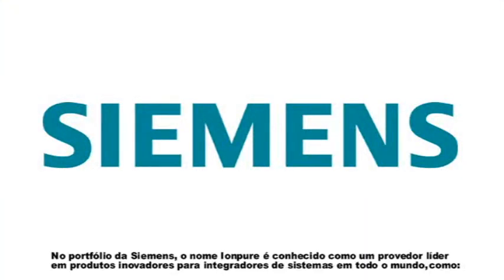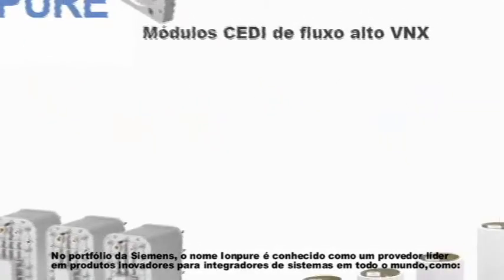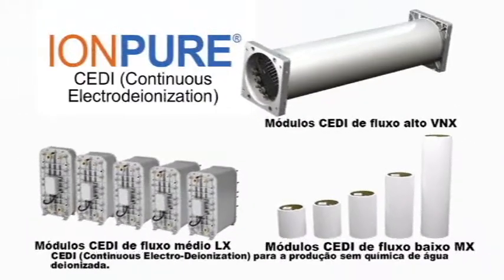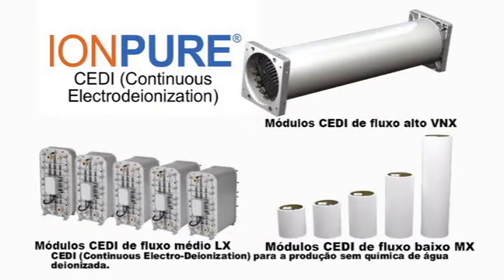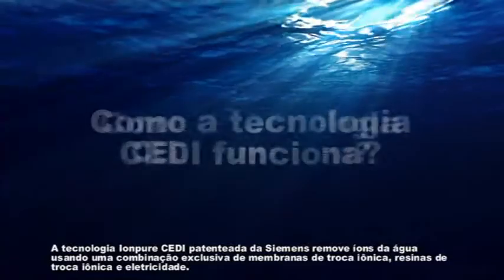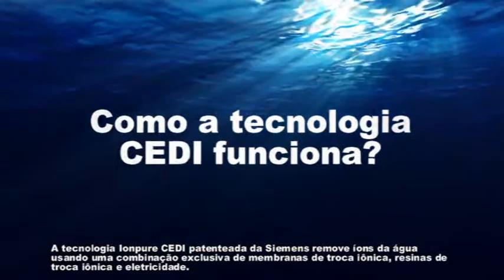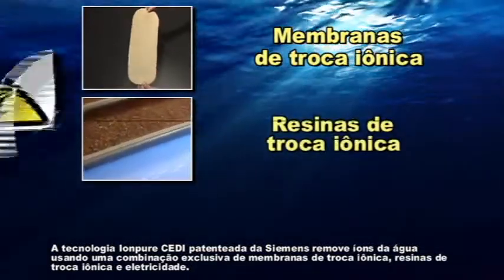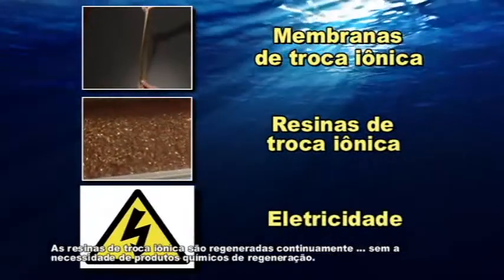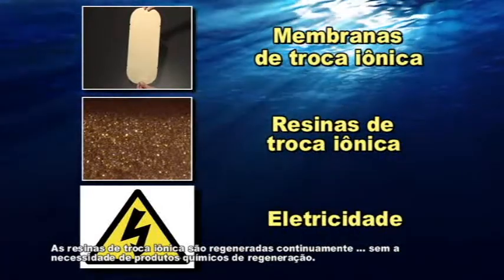In the Siemens portfolio, the IonPure name is known as a leading provider of innovative products for system integrators worldwide, such as continuous electro-deionization, or CEDI, for chemical-free production of deionized water. Siemens' patented IonPure CEDI technology removes ions from water using a unique combination of ion exchange membranes, ion exchange resins, and electricity. The ion exchange resins are continuously regenerated without the need for regeneration chemicals.